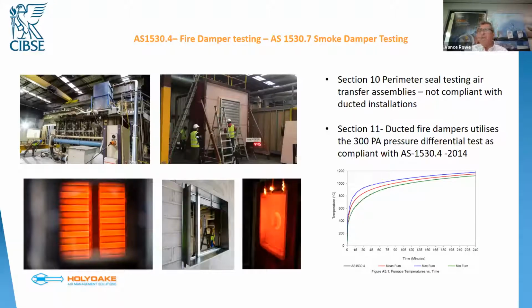Now, a couple of quick graphics up there of testing. Not a lot of people get to see this. I'm one of the lucky people that get to play around with very hot things and spend time at testing authorities. The graphic at the top on the left is the furnace that sits in Warrington's. On the right-hand side at the top, there we are testing. You can see 4 hours, 45 minutes, in fact, a smoke damper and a smoke wall. The graphic down the bottom on the left, that was a multi-section damper test, and in fact, we were testing the mullion for fire dampers at that point.